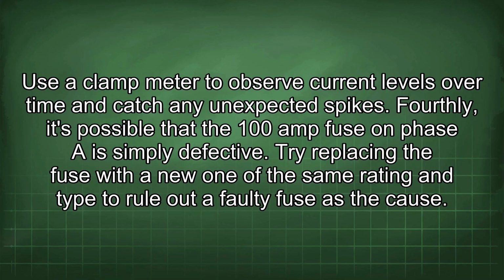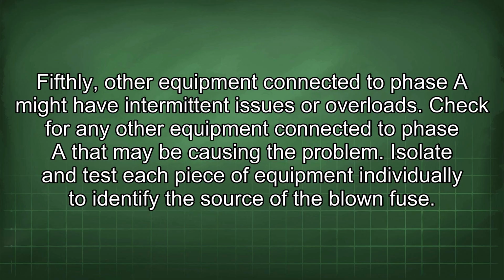Fourthly, it's possible that the 100 amp fuse on phase A is simply defective. Try replacing the fuse with a new one of the same rating and type to rule out a faulty fuse as the cause. Fifthly, other equipment connected to phase A might have intermittent issues or overloads. Check for any other equipment connected to phase A that may be causing the problem. Isolate and test each piece of equipment individually to identify the source of the blown fuse.